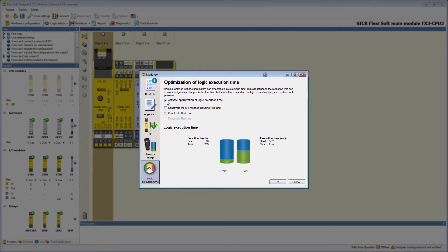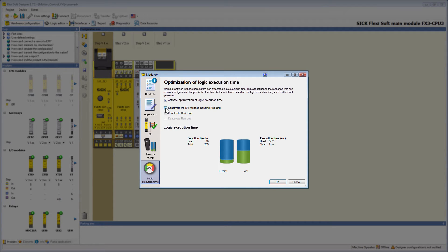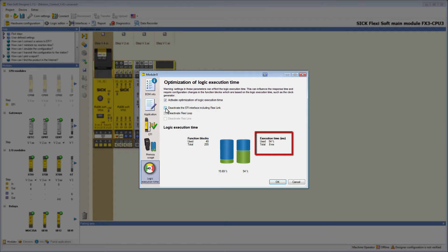To increase the performance of the main module, you can deactivate functions of the CPU which you don't use, like EFI including FlexiLink. By deactivating this option, you can see that the execution time decreases from 8 to 4 milliseconds.